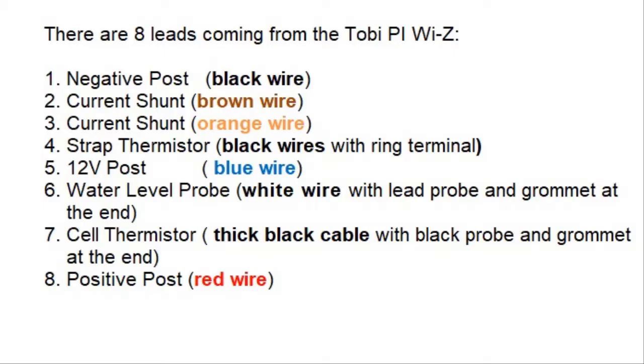There are 8 leads coming from the Tobi PI. Black wire for battery negative, brown and orange wires for current measurement along with the ring terminal thermistor for the current strap temperature, blue wire for battery 12 volt, white wire with lead probe and grommet for water level, black cable with thermistor and grommet for cell temperature, and a red wire for battery positive.